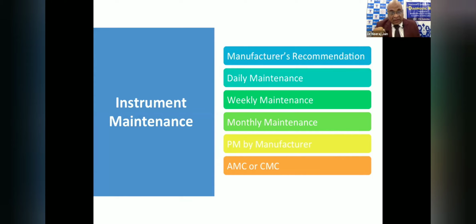Then also see when you are maintaining, because when you are performing tests by colorimeter or semi-automated analyzer, particularly in biochemistry, you can judge many things by seeing the color. But in this automated system, everything is automated, sampling is automated, mixing is automated, and you are ultimately getting results. The instrument maintenance is very important. Follow manufacturer recommendation, what they are recommending for daily maintenance, what for weekly maintenance. You shall have a maintenance schedule: daily, weekly, monthly maintenance, then preventive maintenance by the manufacturer, and you should have an official annual maintenance contract or comprehensive maintenance contract in which part cost is also included.